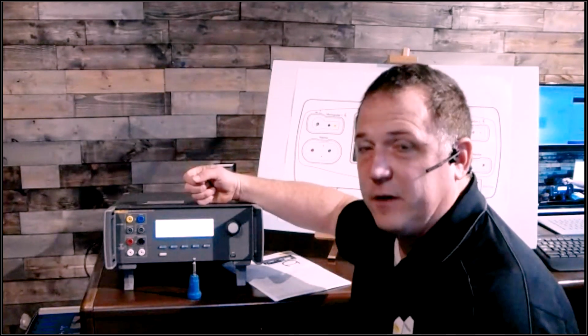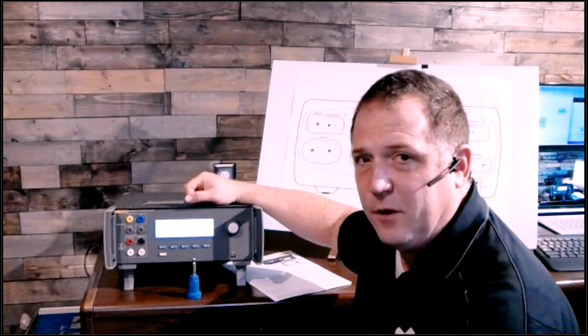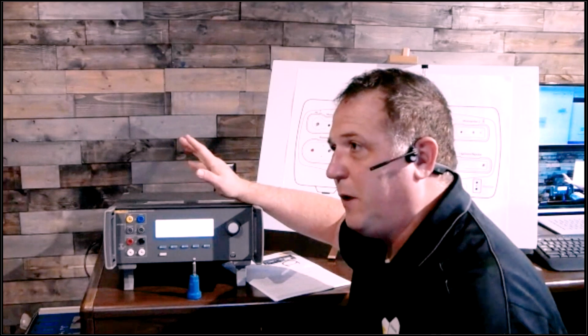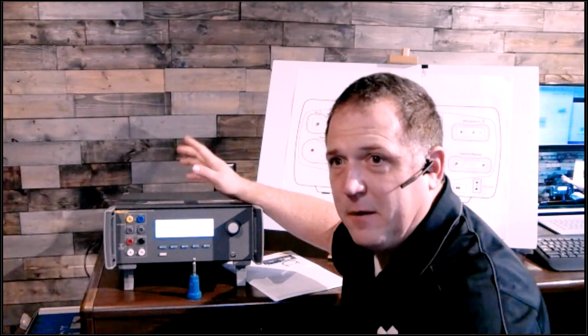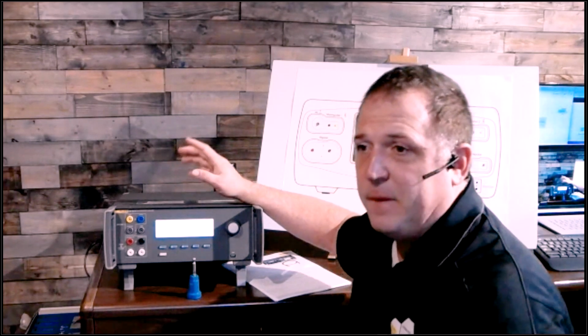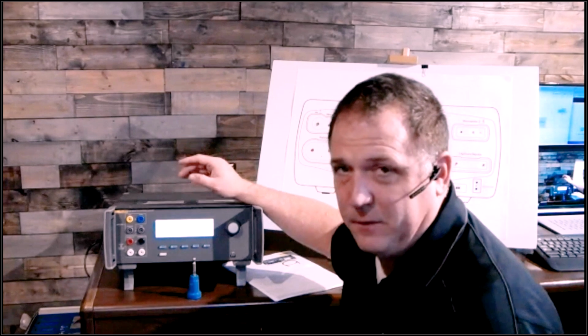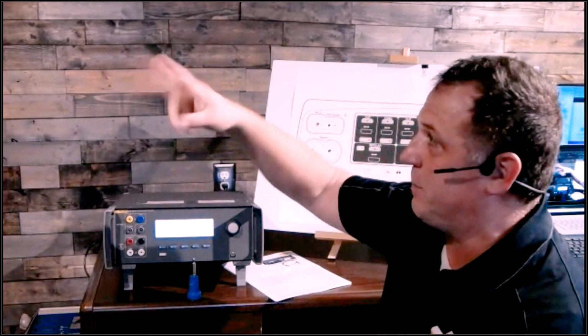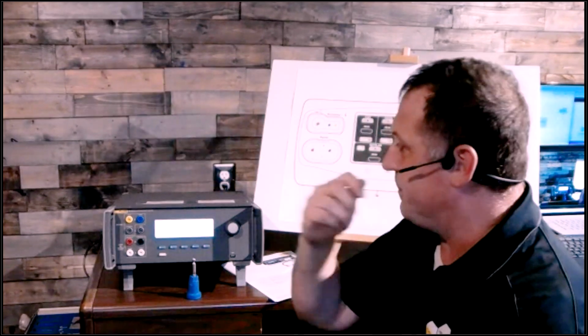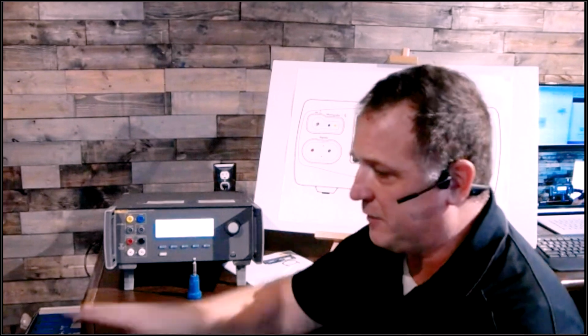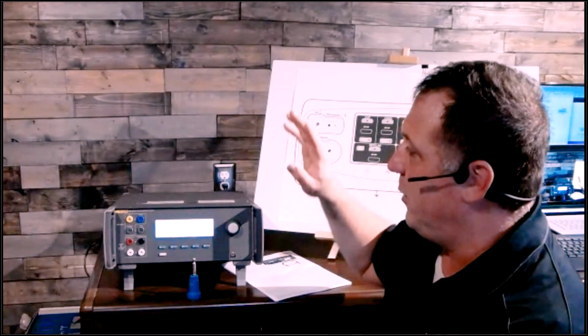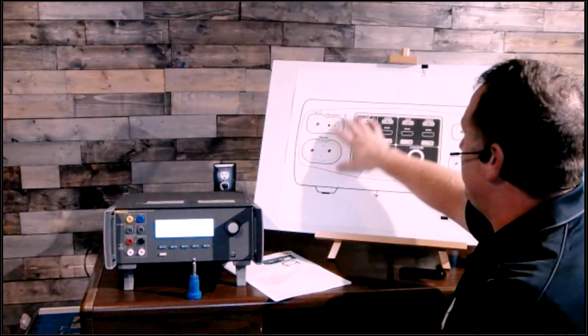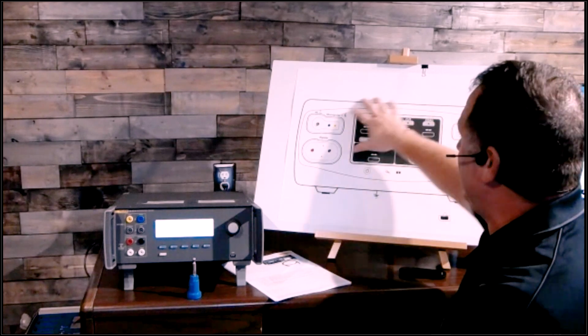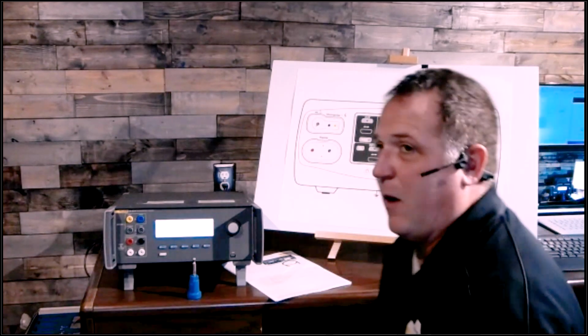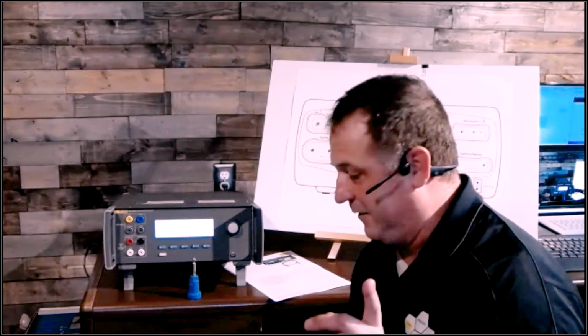Your ESU, though, is operating probably somewhere in the 2.5 to 3.5 megahertz range. So energy responds differently at that high frequency, where it's flip-flopping its polarity super, super fast — it responds and acts differently. So not only do we have to check to make sure the line voltage, or 60 hertz energy, isn't leaking to the outside of the chassis, we now also have to check that high frequency energy is not leaking to the outside of the chassis.